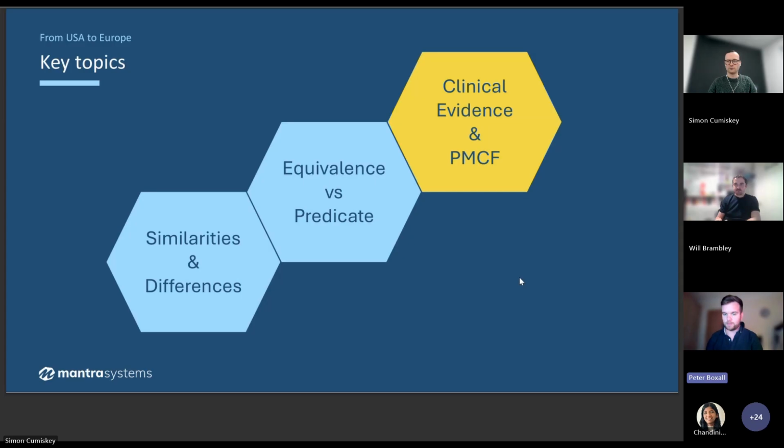And we also need to use clinical evidence to demonstrate conformity with the general safety and performance requirements of the EU MDR, something that Simon alluded to earlier. Generally speaking, that's using the evidence in the ways that I've discussed previously: suitability for intended purpose, that you've met quantitative objectives relating to real-world evidence of similar devices out there, that you have an acceptable benefit risk profile. So these are the ways that you need to use clinical evidence in your initial submission.